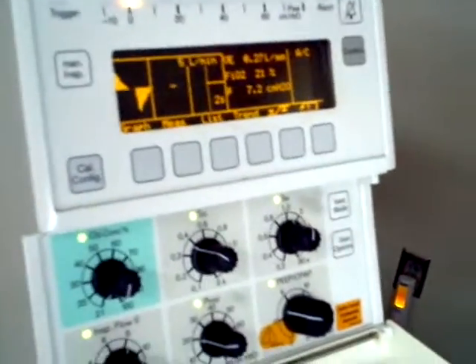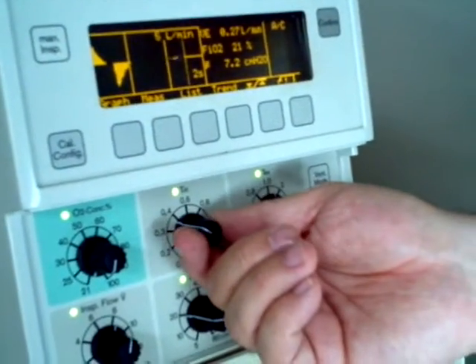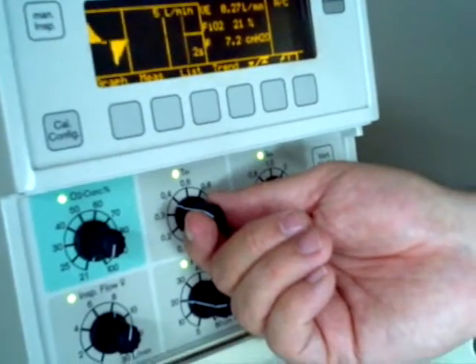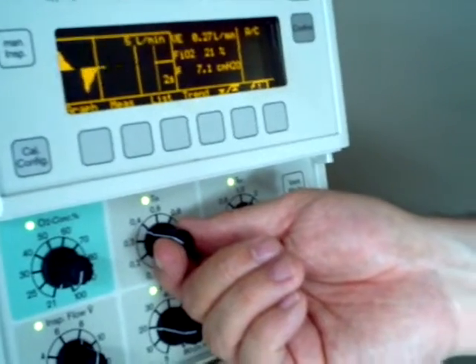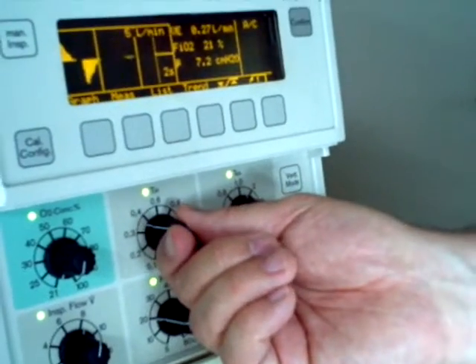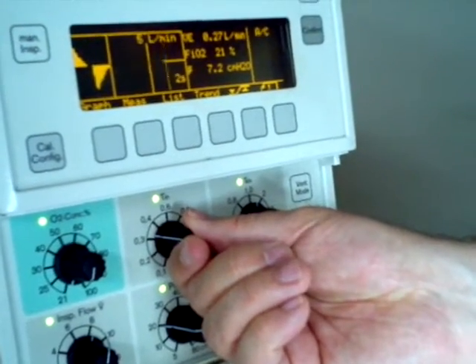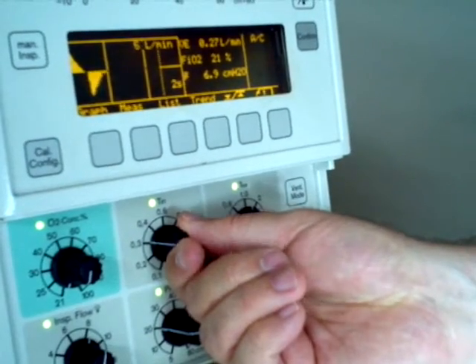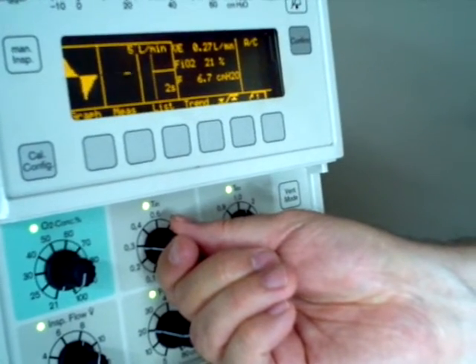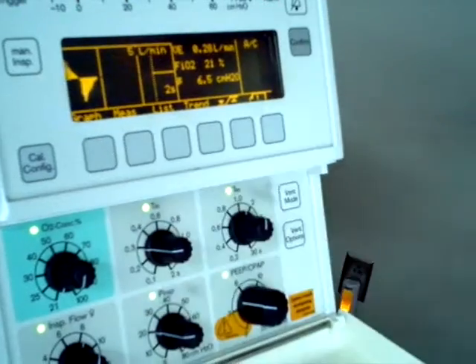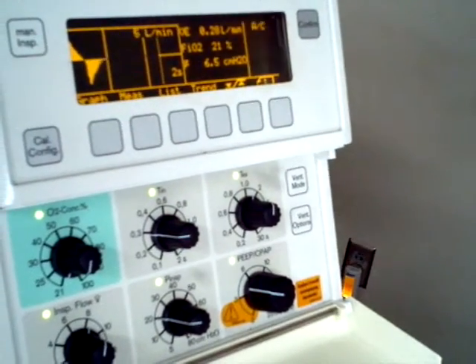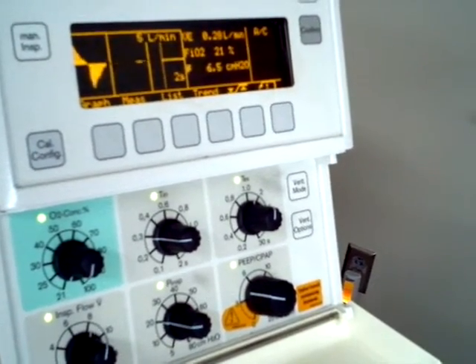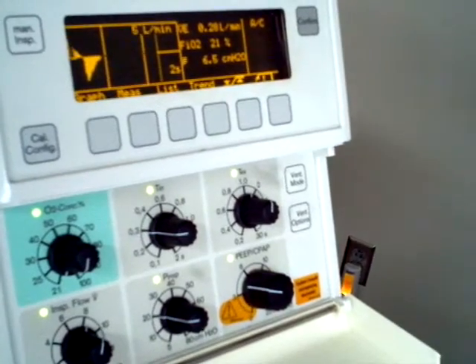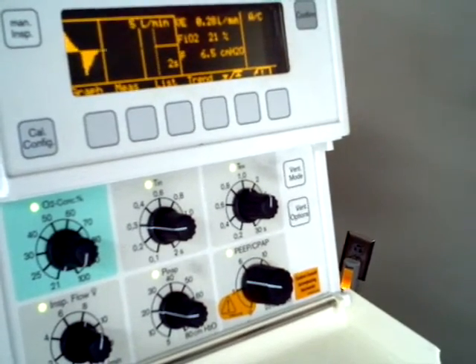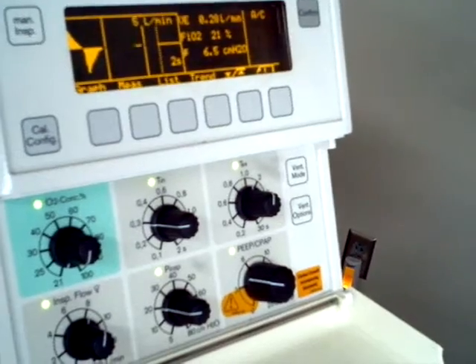Shorten my inspiratory time. So this is one of the other 3 things that's nice about the Babylog. It gives us real-time measurements. So if I shorten my inspiratory time, you'll watch those 2 curves get closer together. And that looks pretty. The other thing we're doing here is making more of a sine curve and less of a square curve on our pressure curve. All right? Maybe a little bit of pause, but I like that.